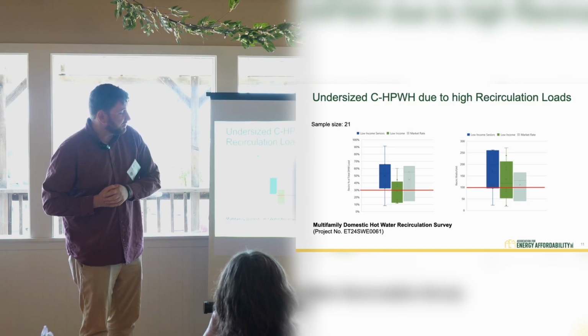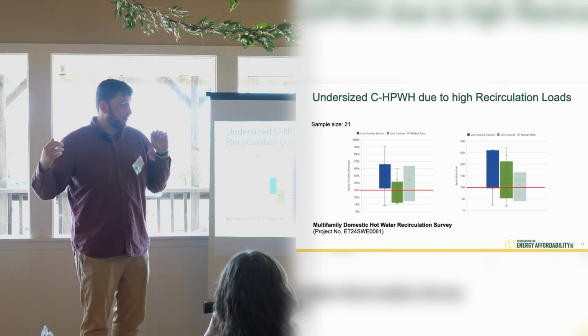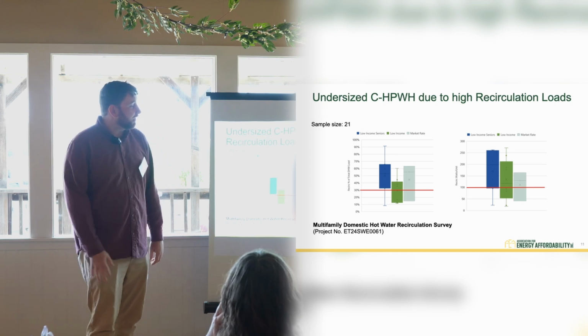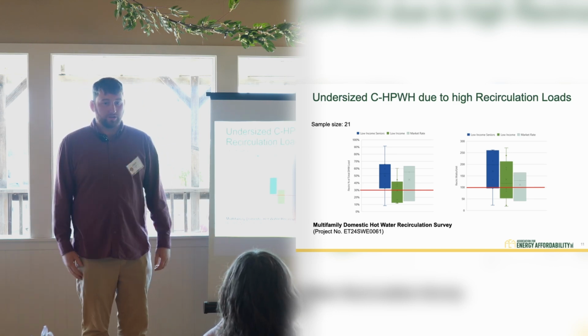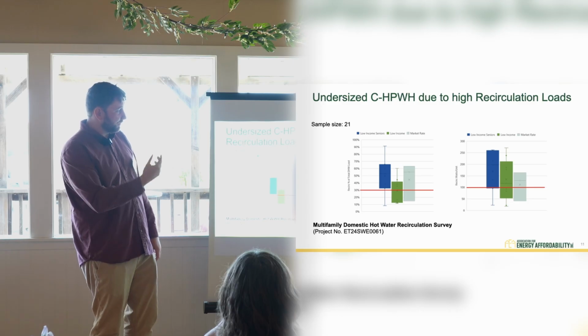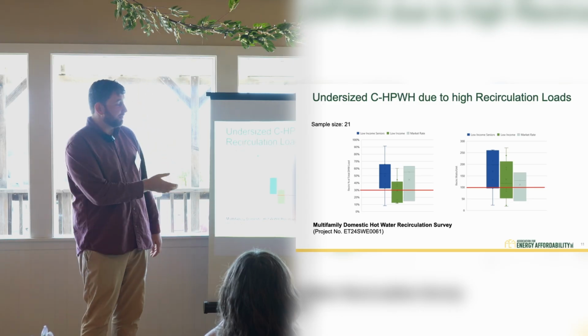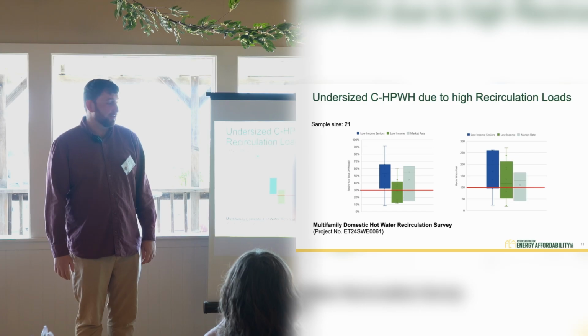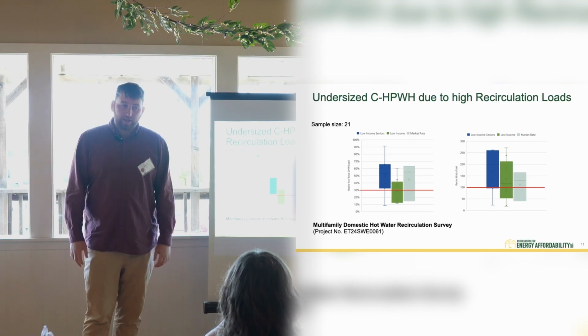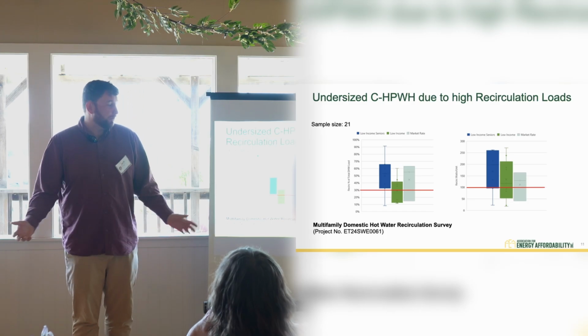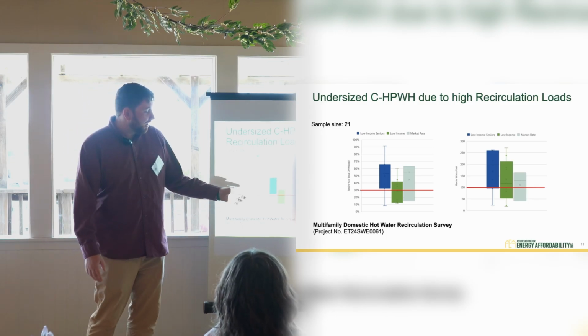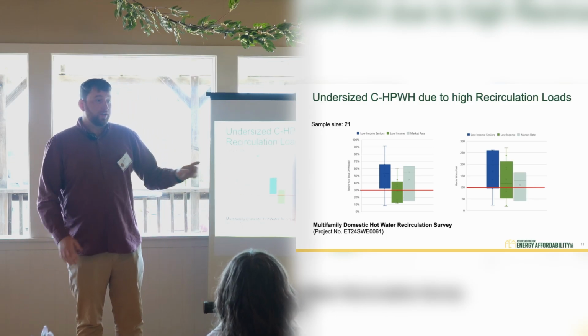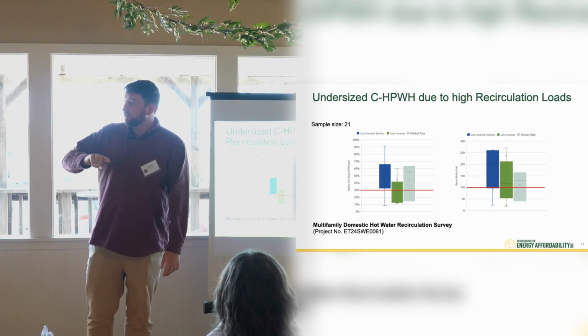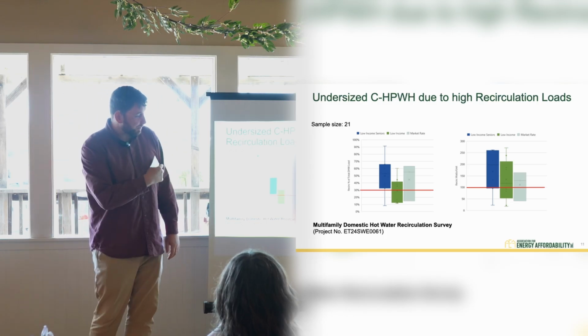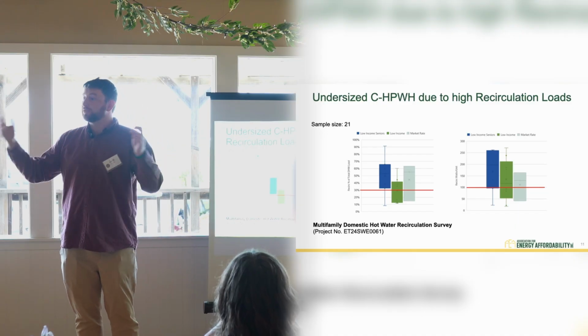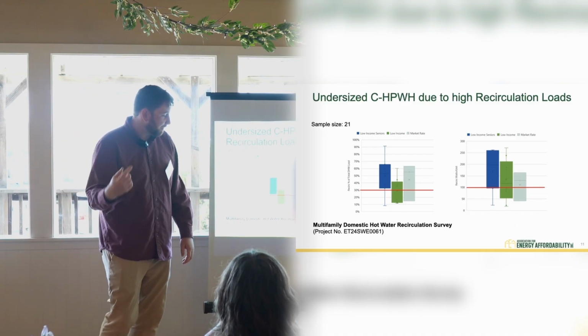This is something that is really dear to my heart, and some of the things that I work on most of my time at AEA is talking about recirculation loads. So one of the reasons why a central heat pump water heater fails, and trust me, I know because I've worked on them that have failed, is because we're sizing them incorrectly. And we're not sizing them incorrectly because we don't know what we're doing. Well, we might not know everything, but we don't know what the recirc loads are. In every central domestic hot water system, you have a hot water line going out, hot water coming back.